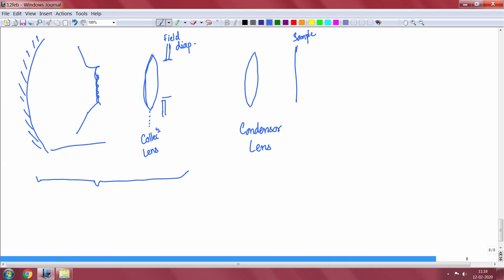Once the field diaphragm is uniformly illuminated, a condenser lens images the field diaphragm onto the sample plane. Since at the field diaphragm there is no image of the filament — the image of the filament is formed at infinity after the collection lens — we do not have to worry about the filament image. All the photons collected pass through this aperture, making it bright and uniformly illuminating the sample.